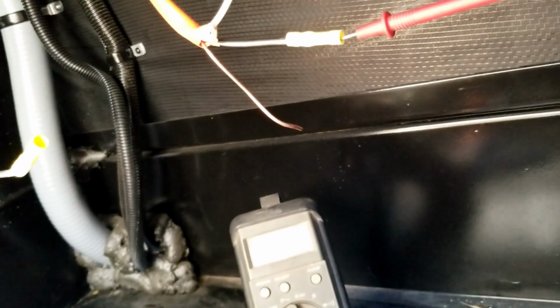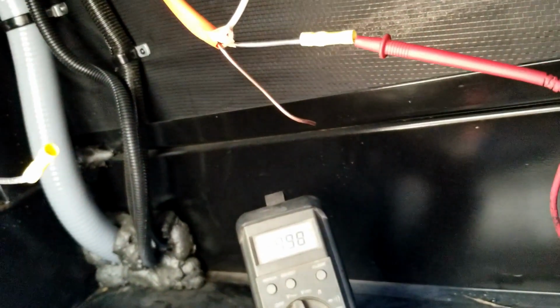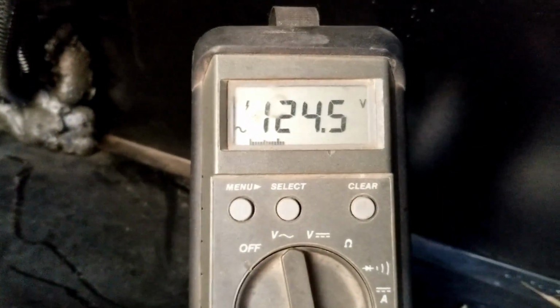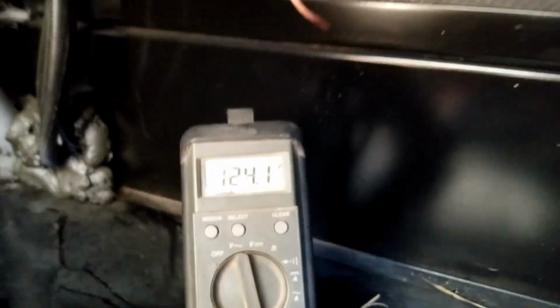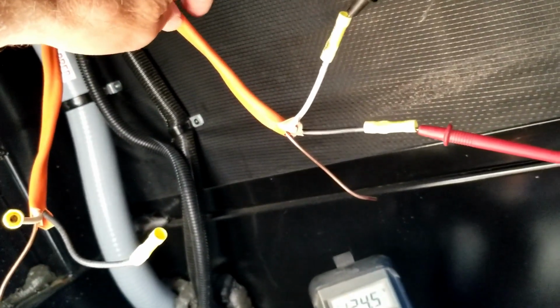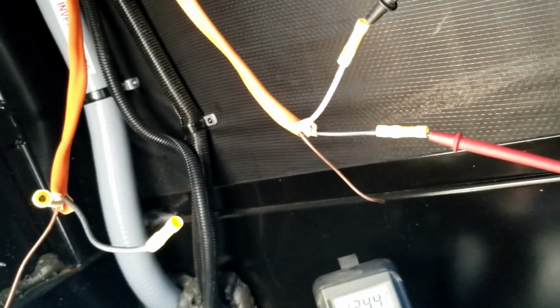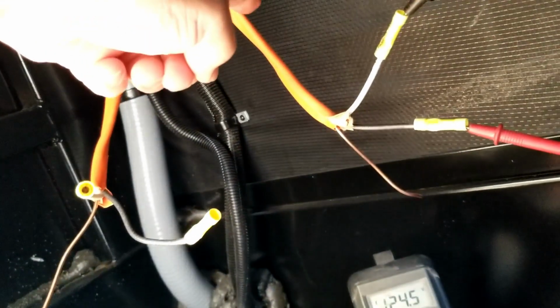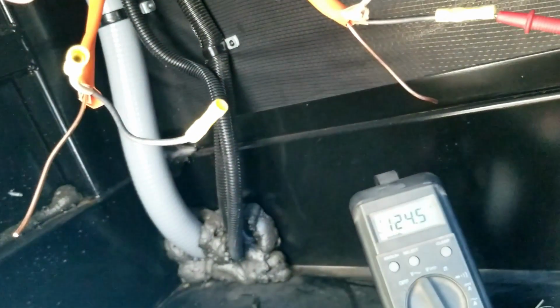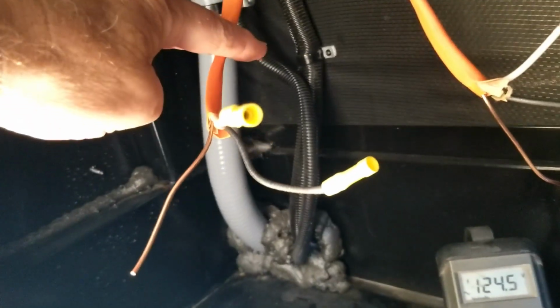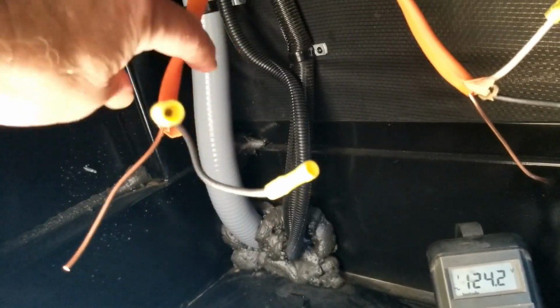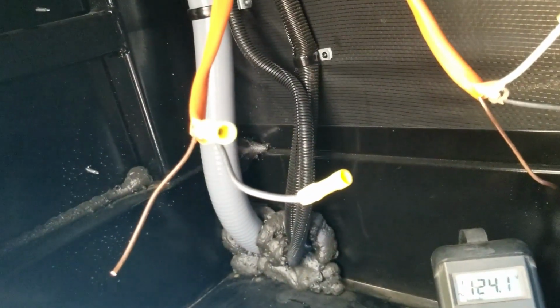And this wire I would expect to see 120 volts on. And there you go, 124.5 volts. So this wire is connected to that first 30 amp circuit breaker inside the panel. Originally it was looping the power back to that second 30 amp circuit breaker. So this wire, because it doesn't have any voltage on it, is connected to that second 30 amp circuit breaker.